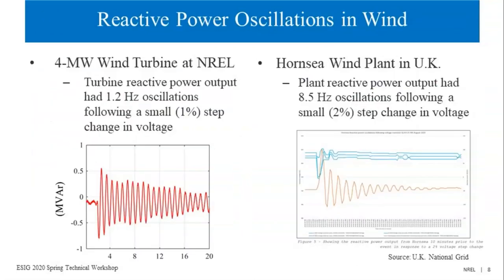When we tested this turbine in the laboratory, we found that indeed the wind turbine has a reactive power oscillation mode. The bottom left plot shows the reactive power output of the wind turbine when the voltage at its terminal was given a step change of just 1%. The behavior resembles very closely what was described in the report that came out from National Grid, showing reactive power oscillations in the Hornsea wind plant in the UK for 10 minutes before the blackout in August last year. So this is a very interesting and practical problem.